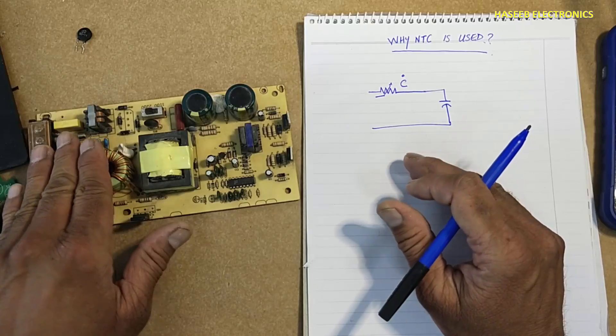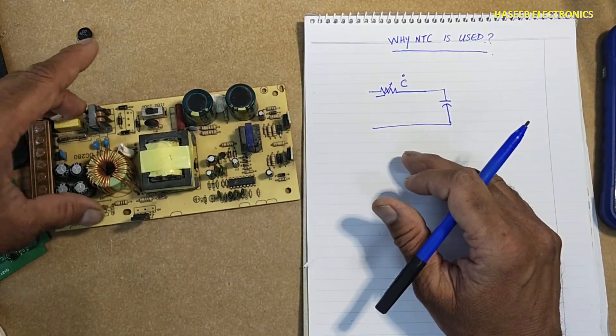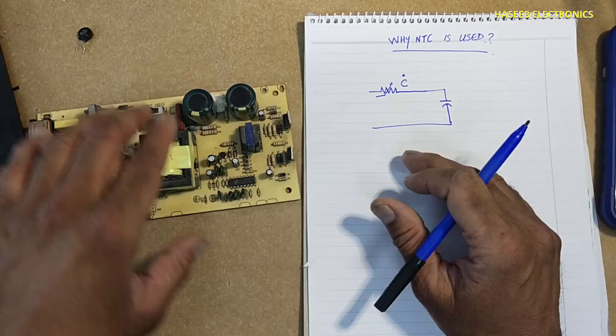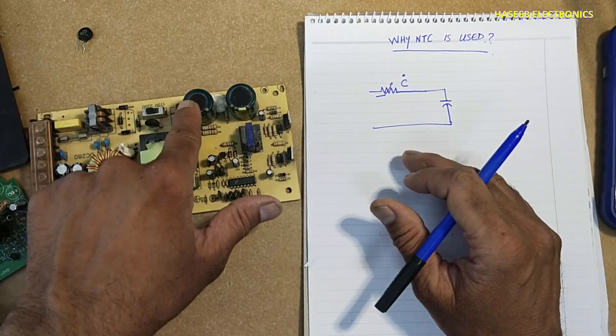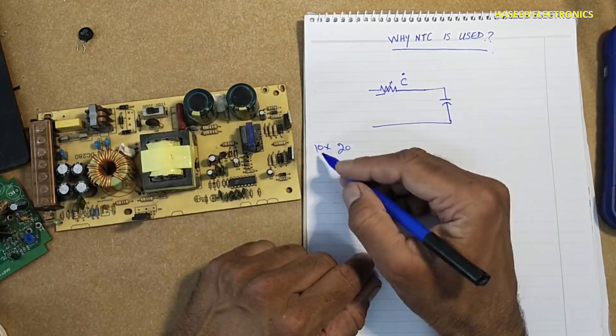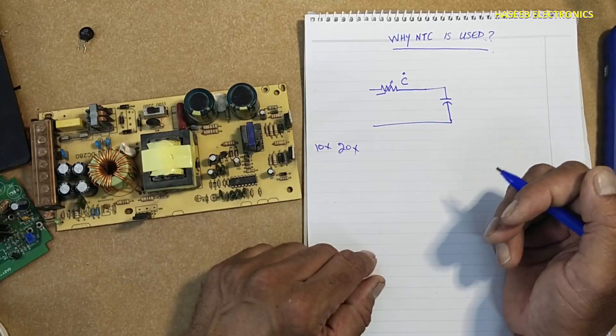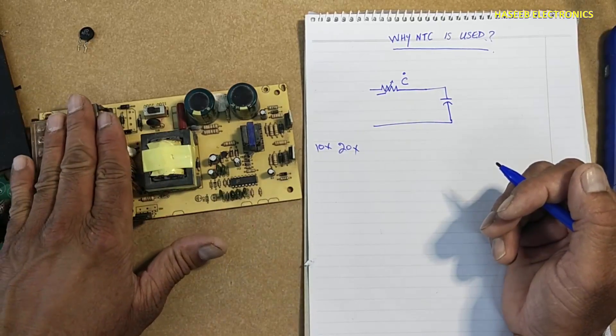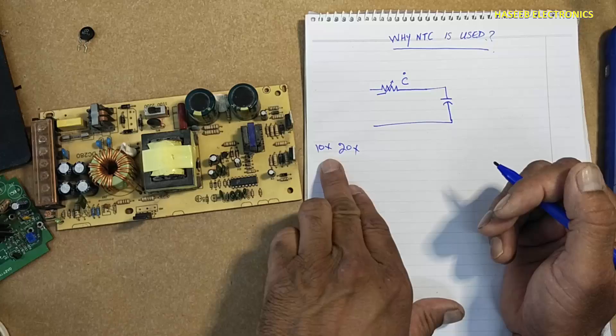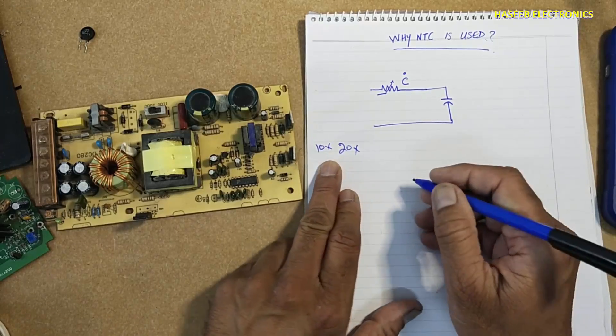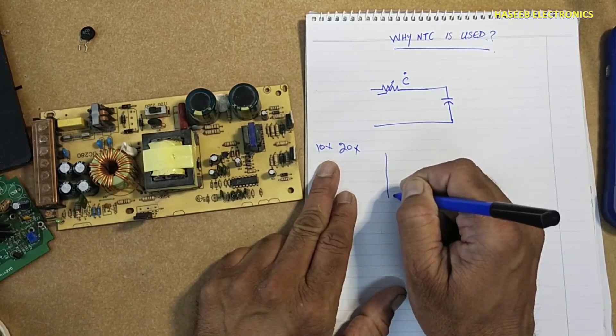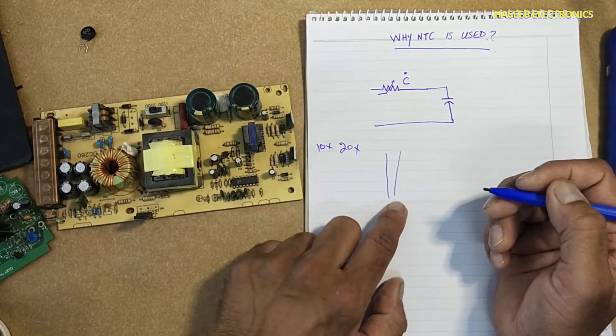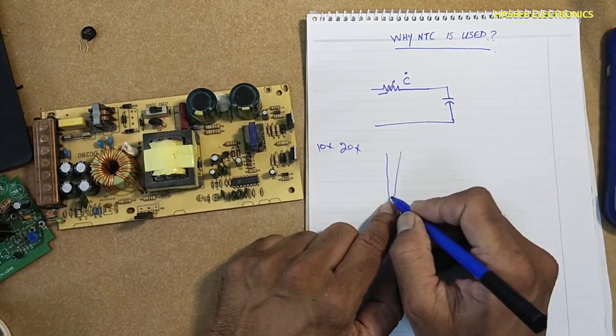Current, for example the routine current for this power supply is 2 ampere. At that time, its current will increase 10 times to 20 times. We can say normal current 2 ampere, 10 times it will increase up to 20 ampere. Initially, initial charging current when power supply is powered on, then it will back to normal.